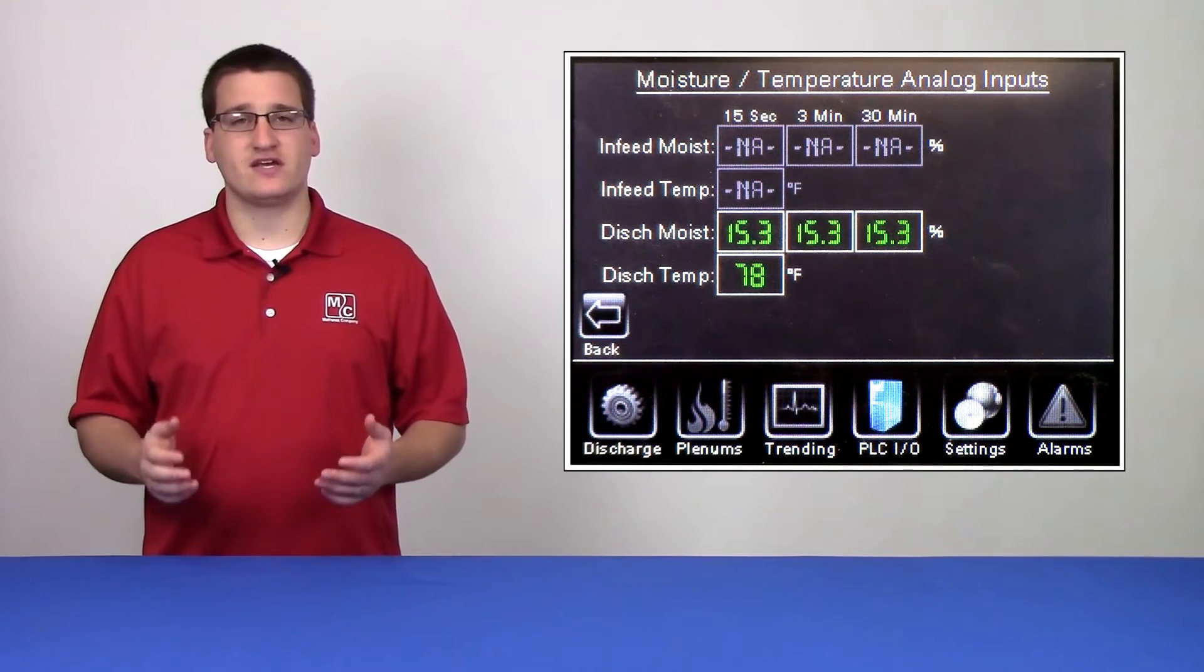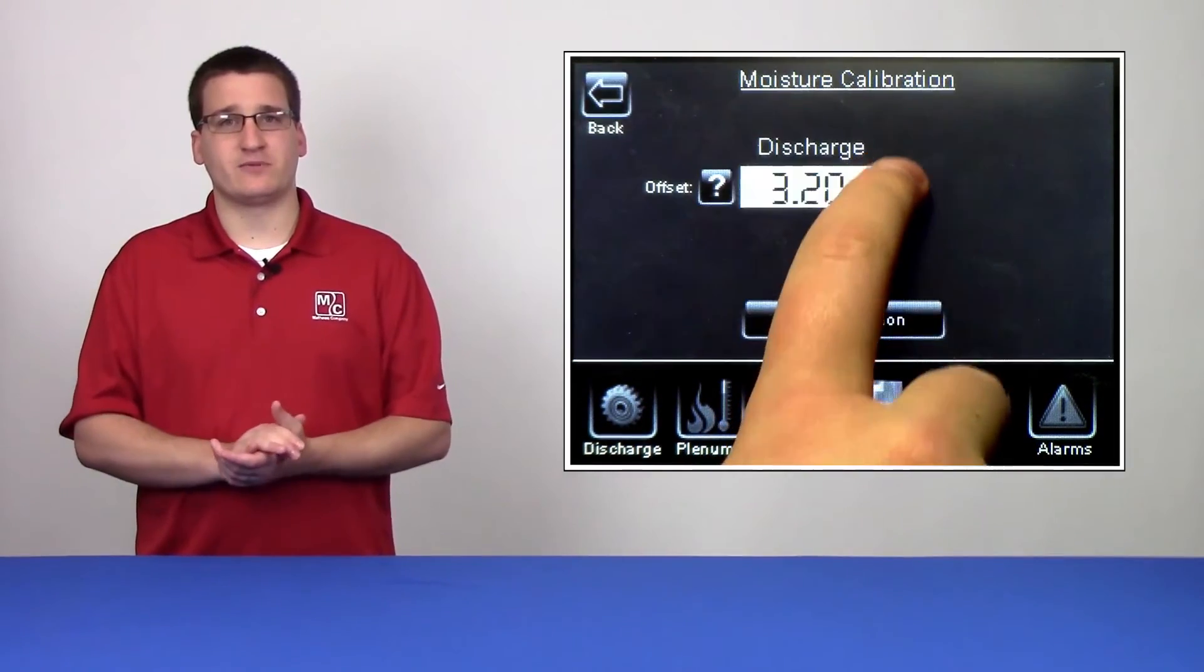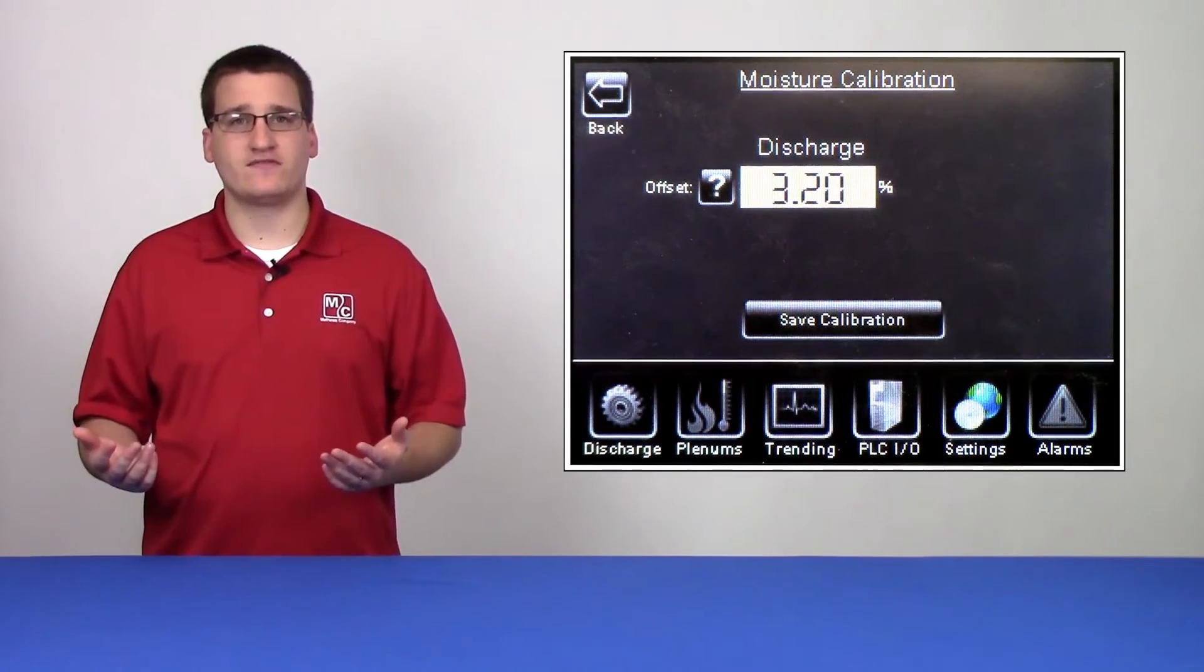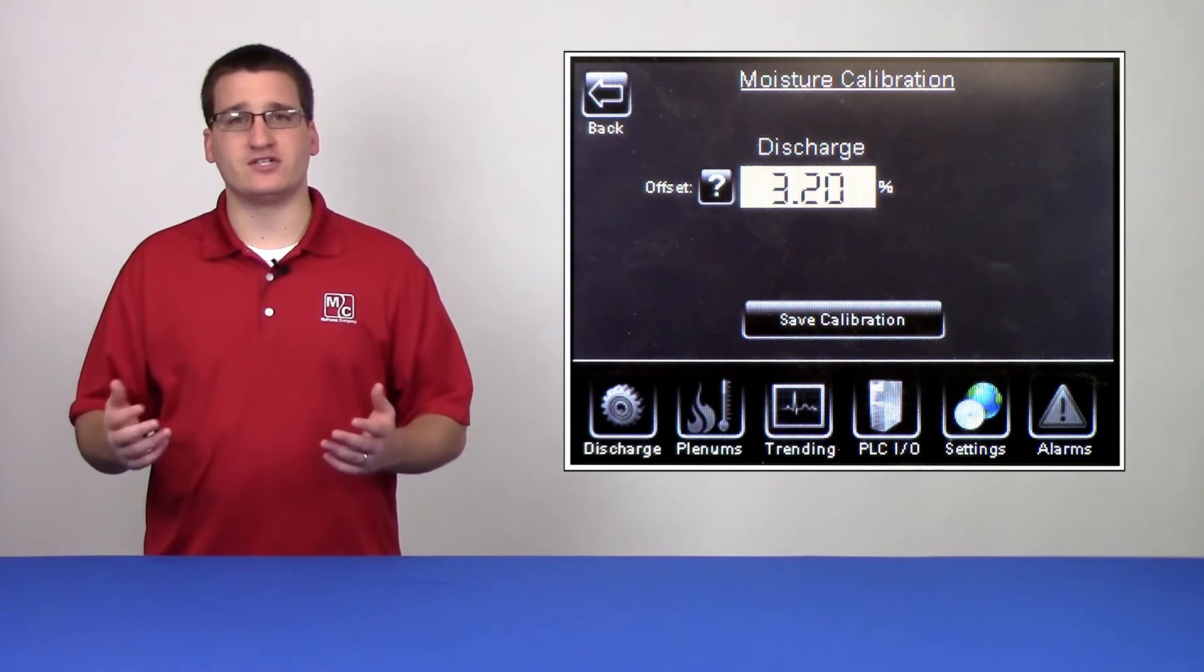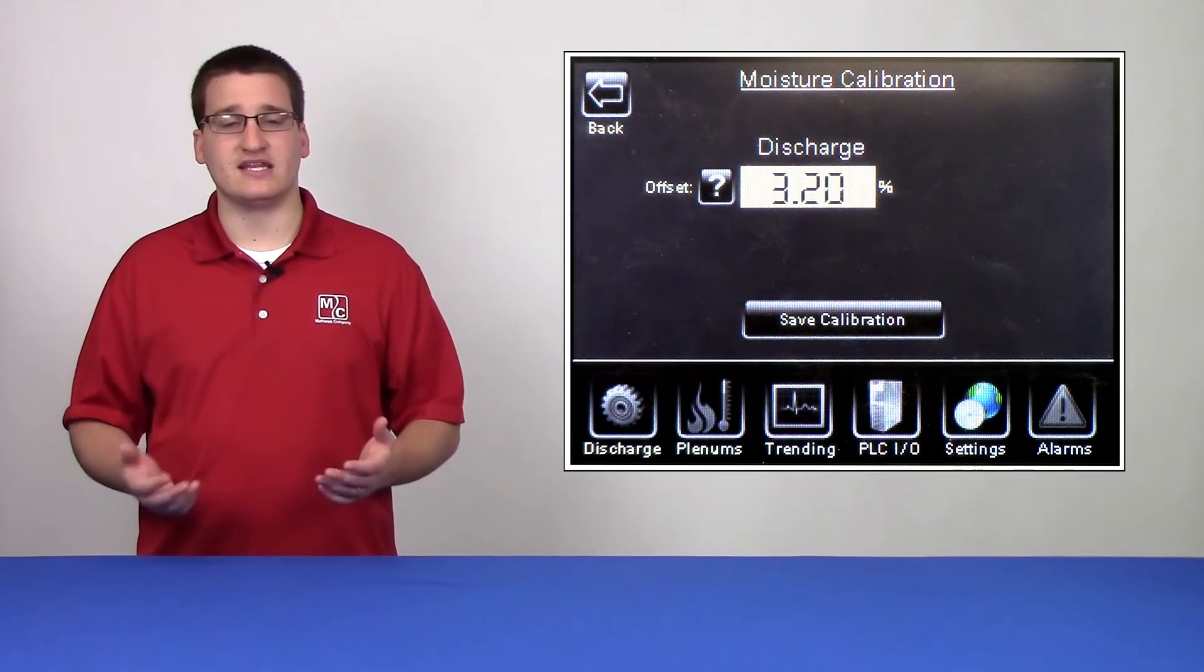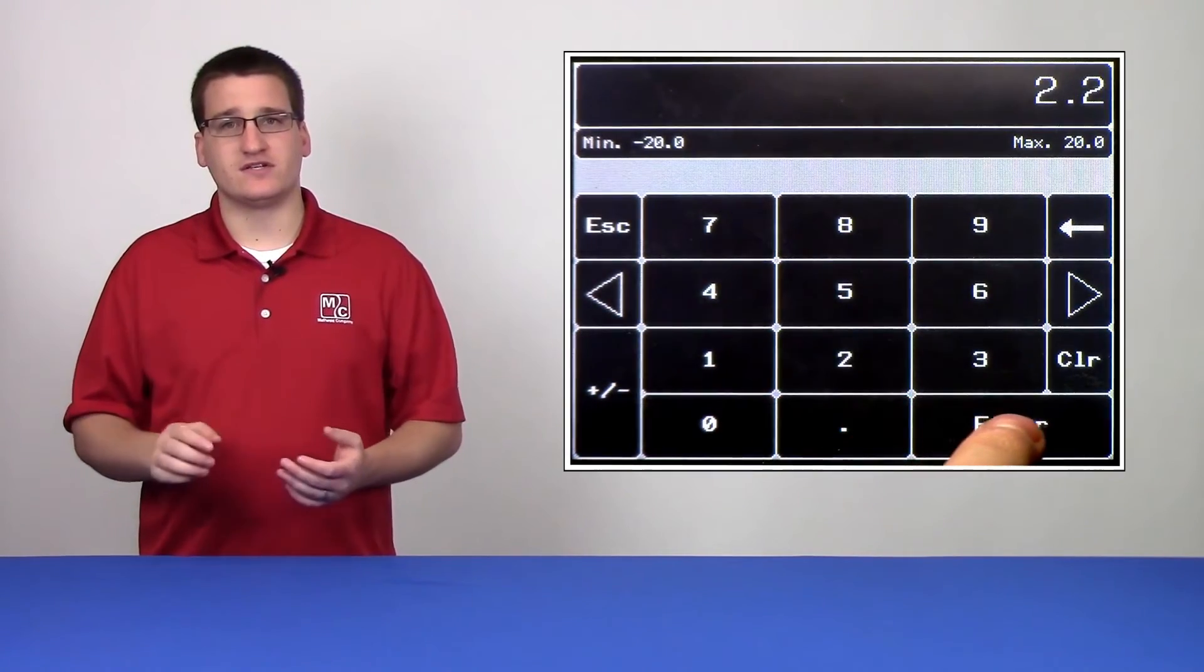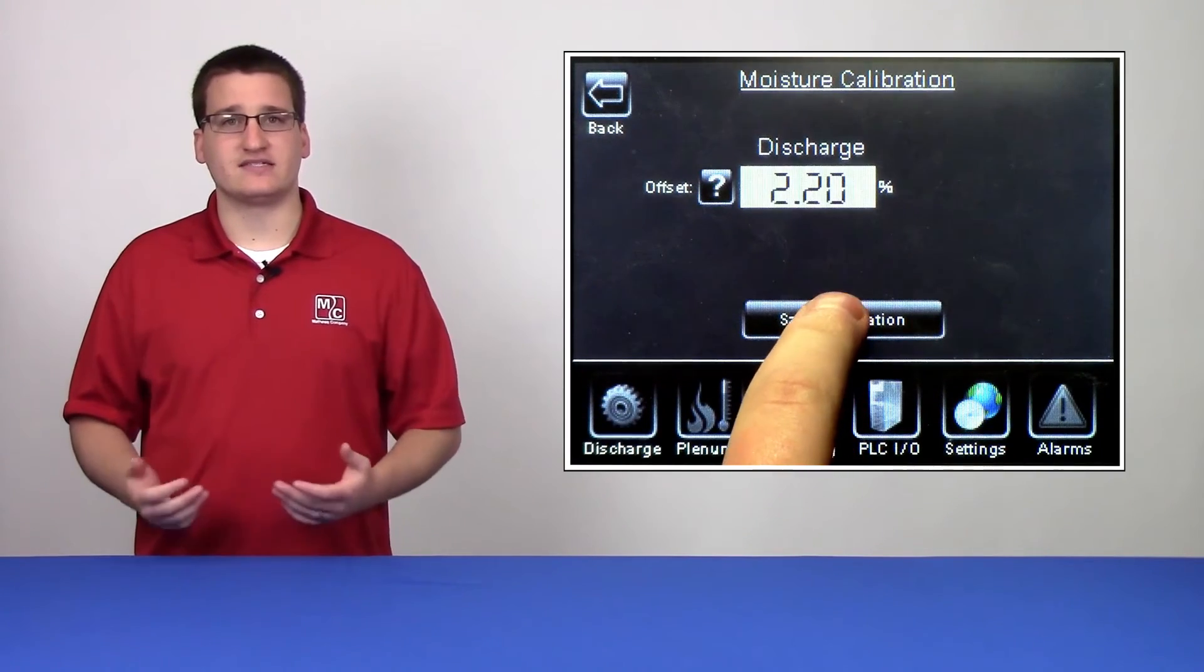To fix this, you go to the HMI, hit settings, and then sensor calibration. You'll notice that there's an offset field. We want to adjust this offset by the difference we calculated earlier. In this case, we want to change 3.2 to 2.2 and hit save calibration.